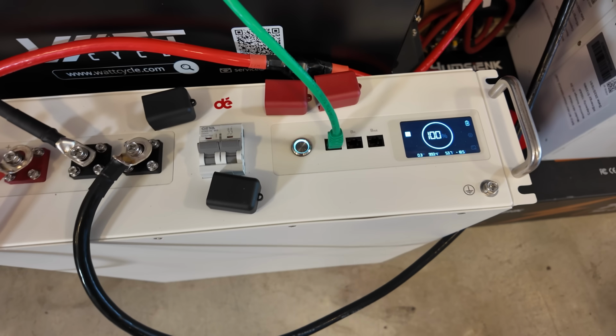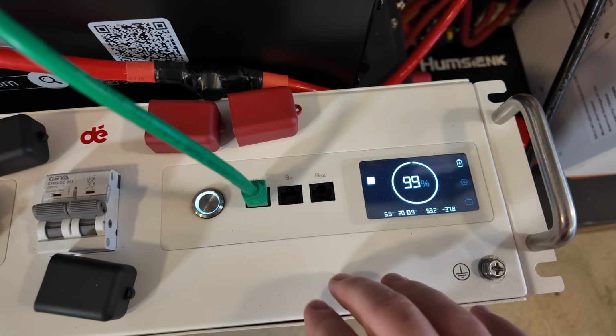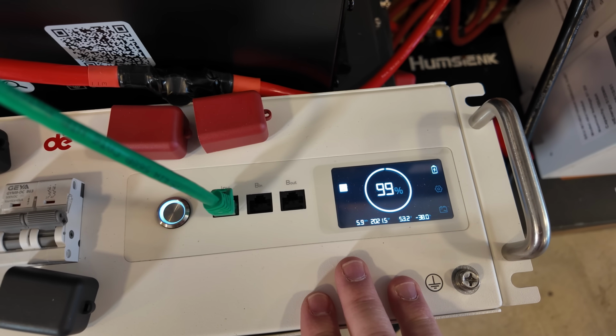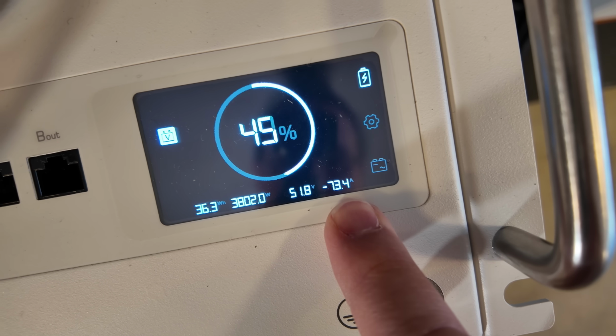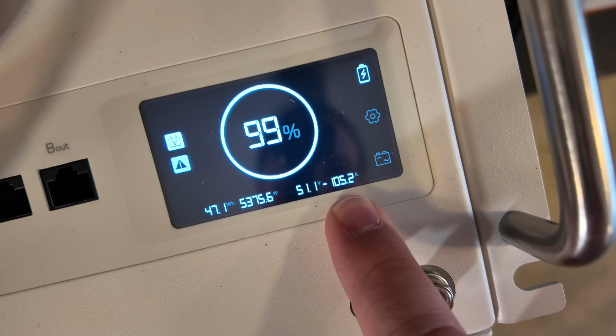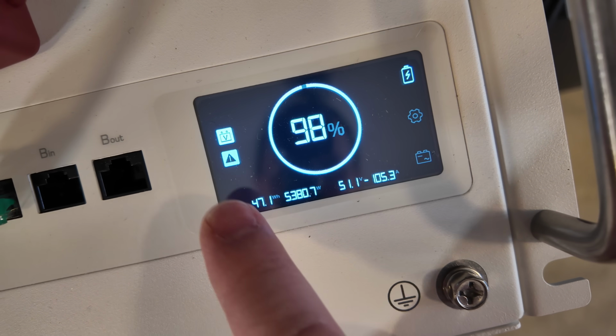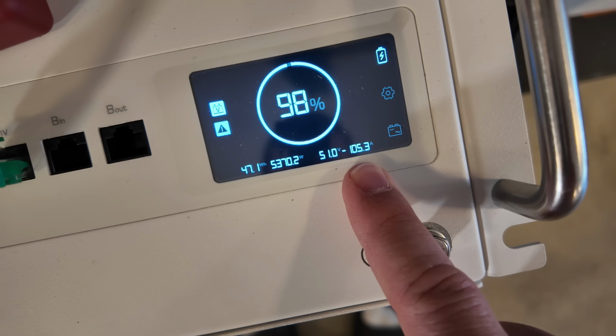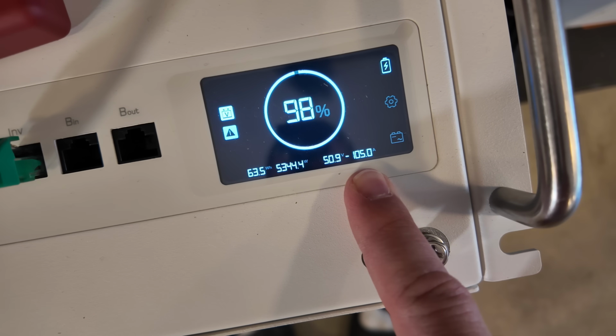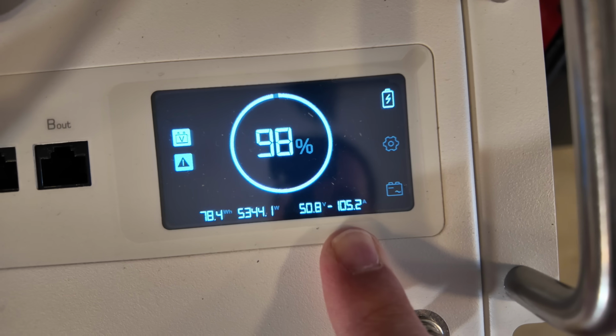So next, we're going to push this battery with a heavy load as close to 100 amps as we possibly can. You can see our amps are in the low 70s. Let's give it some heat gun. 105 - we have a warning here, it may shut down, we will see. 104, 105 amps still - it's running it.